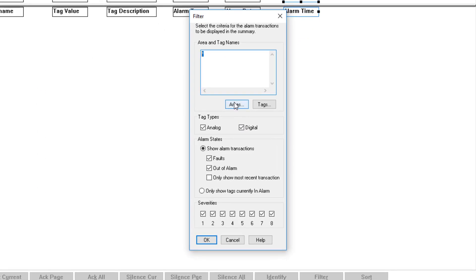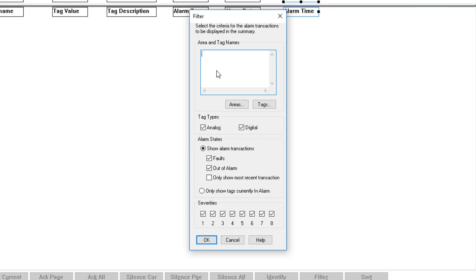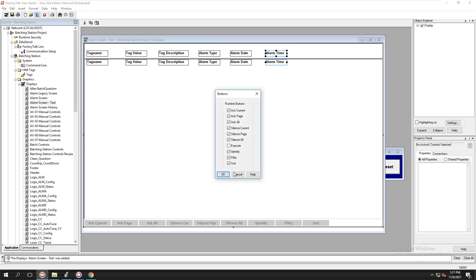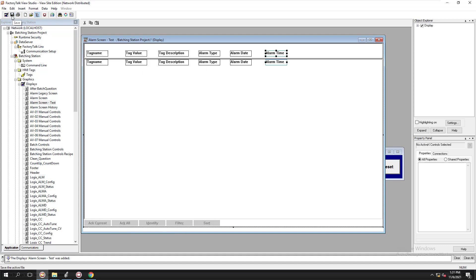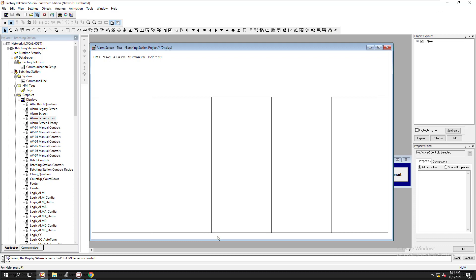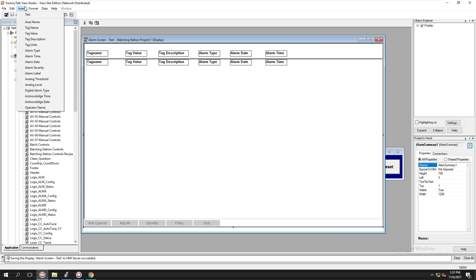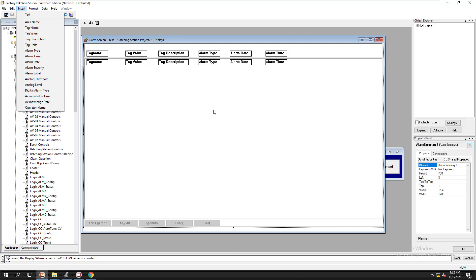This is where you format and set your filter. Your filter is your area — so if you're passing a parameter through a button to call up different areas, make this a number one and put that in there. That's key to getting the communication working when passing parameters. For the buttons, you can remove ones you don't need — like silence and page acknowledge — which shrinks it down. All formatting options are available up in the Format menu.